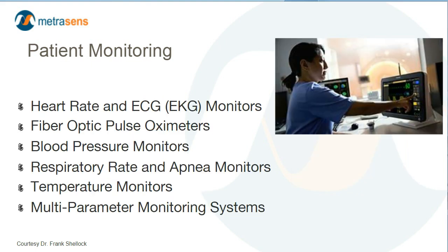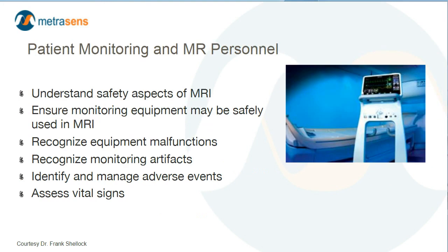MR conditional physiological monitoring equipment can include heart rate or EKG monitors, fiber optic pulse oximeters, blood pressure monitors, respiratory rate and apnea monitors, temperature monitors, and multi-parameter monitoring systems. With regards to monitoring patients in MRI, MR Level 2 personnel should understand safety aspects of MRI, ensure monitoring equipment may be safely used in MRI, recognize equipment malfunctions, recognize monitoring artifacts, identify and manage adverse events, and assess vital signs.